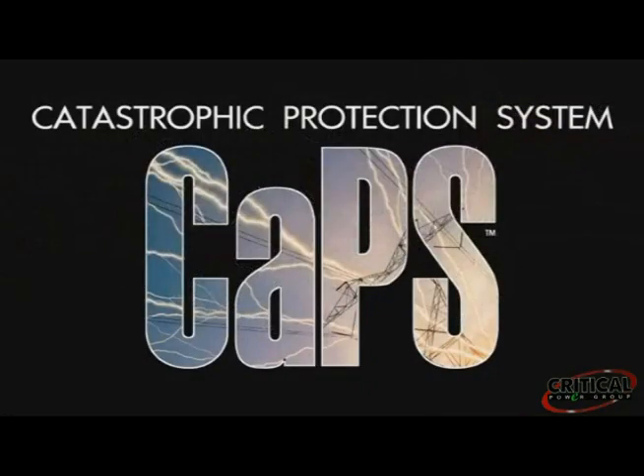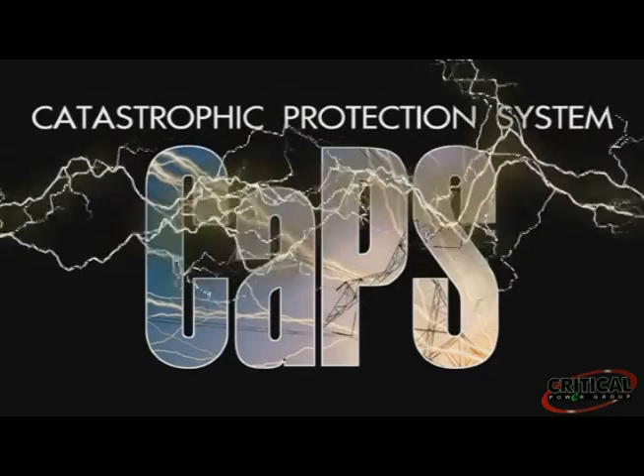According to power quality experts, while lightning is the most common source of failed equipment, TOVs and sustained overvoltage events will be the most destructive power quality events over the next 10 years. So how can you protect against TOVs and sustained overvoltage events? You might install a UPS system at a cost of $100,000 and upwards, or you might try a voltage regulator, but they're large and use fairly old technology. Or you could try the catastrophic protection system from current technology.